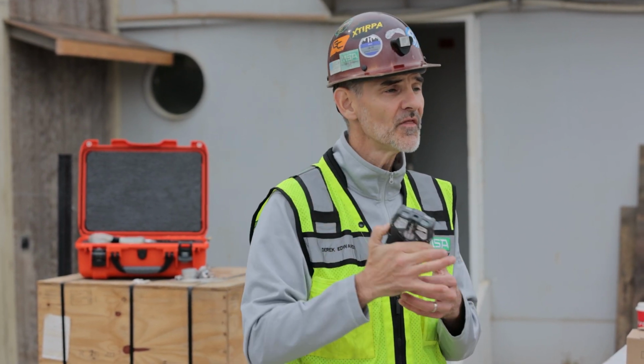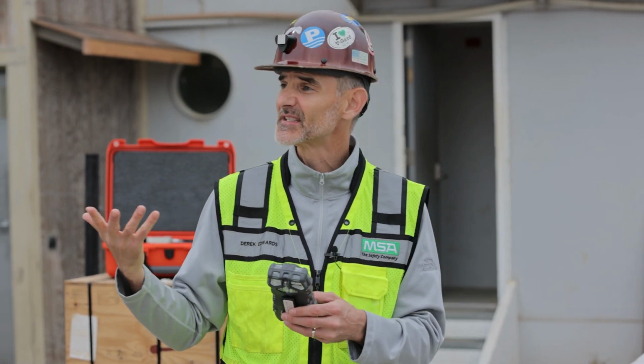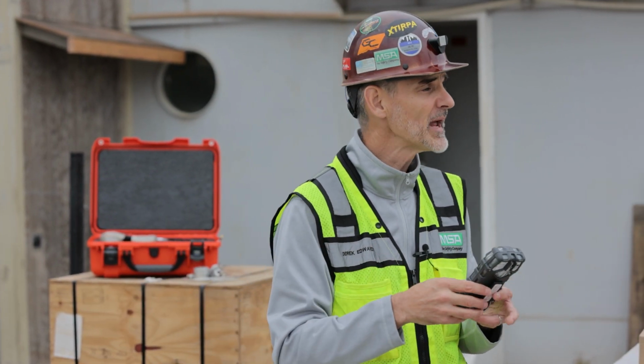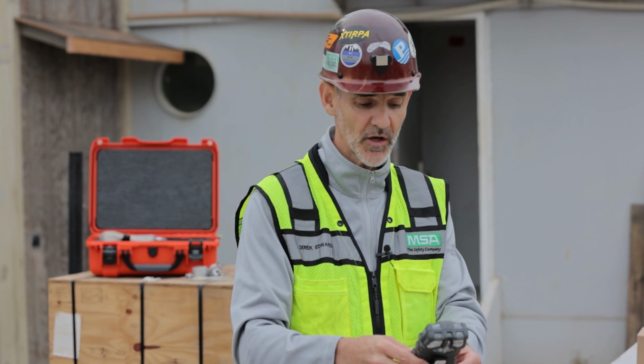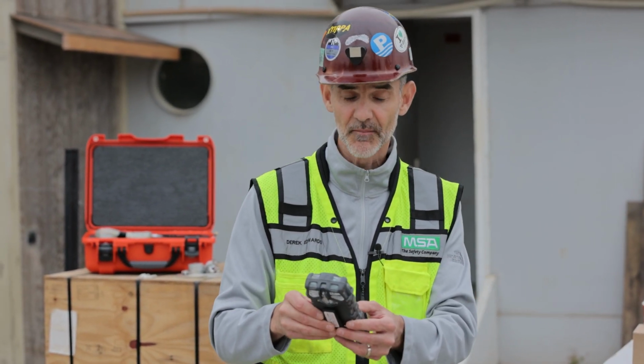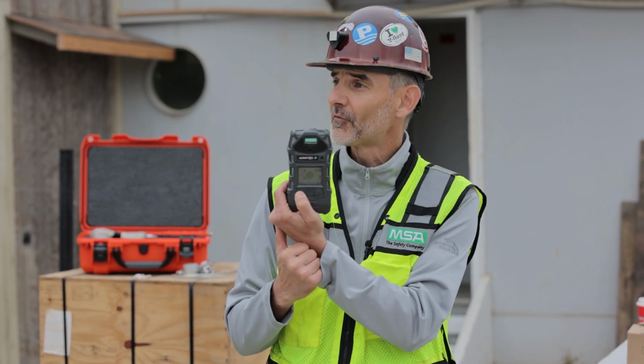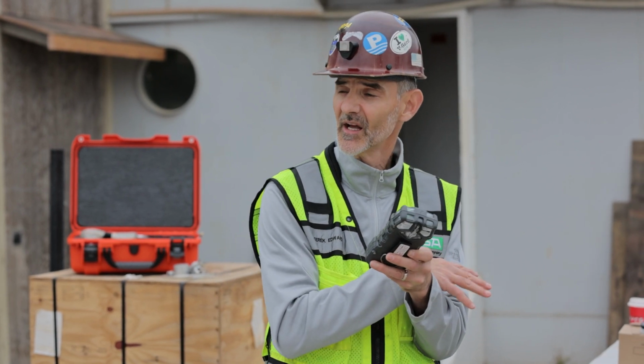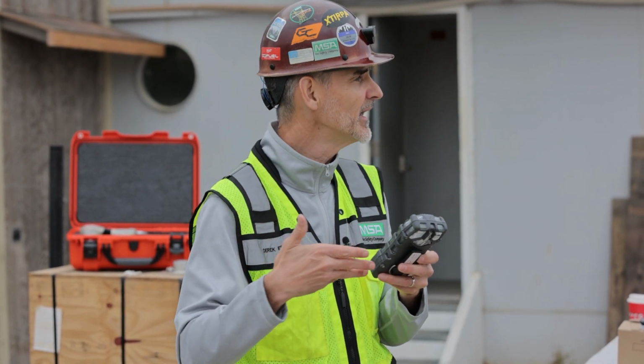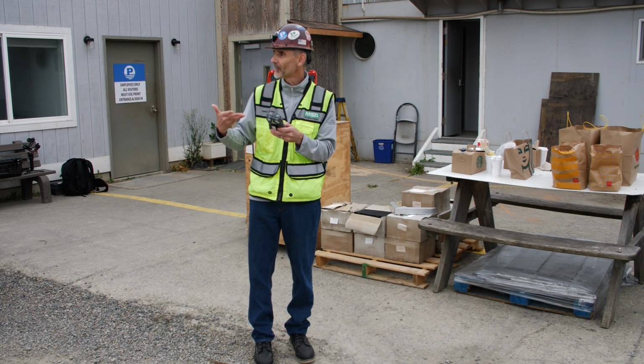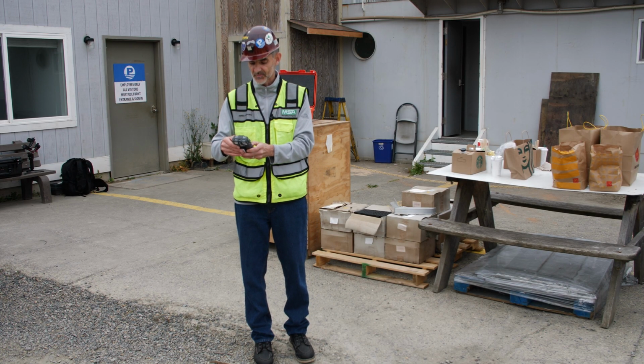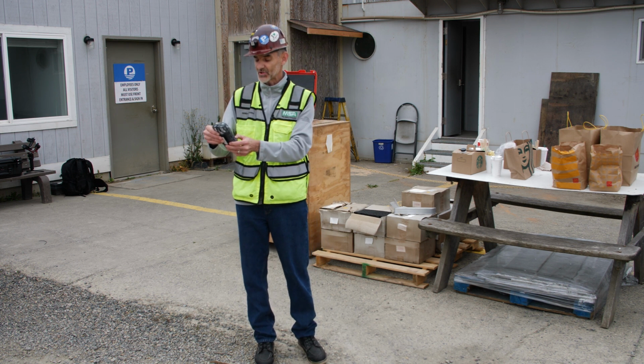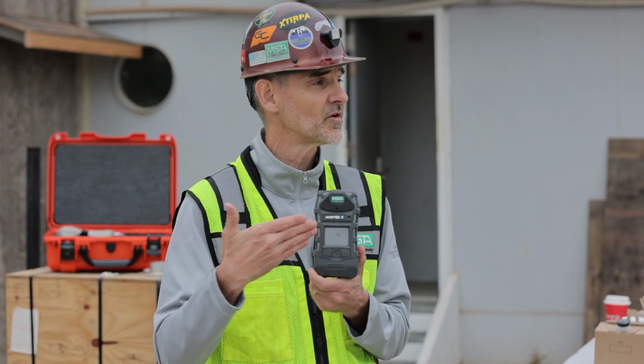Okay? There's a couple of buttons you can push on this instrument to see information. The right button is our mode button. If we look at the instrument, it says bump just above the left button there. If we press that, we're going to do a bump test, which we'll do in a second. If you continue to press that button, it's going to continue to show you information. One of those pieces of information is the alarms, okay? Push it twice, it's going to show the peak reading, which is the highest level of alarm that it's seen since you turned the instrument on.